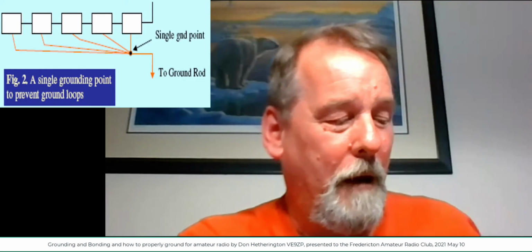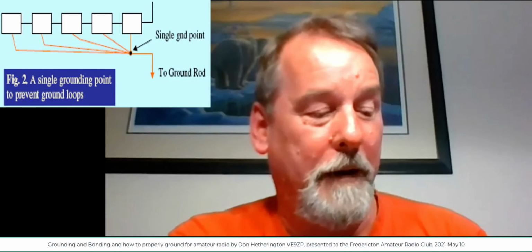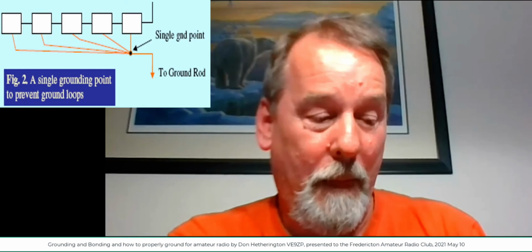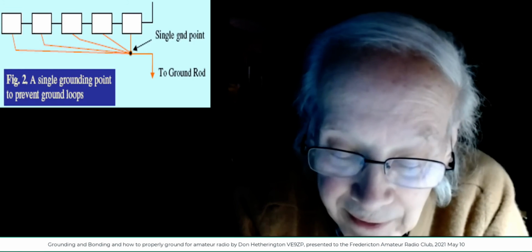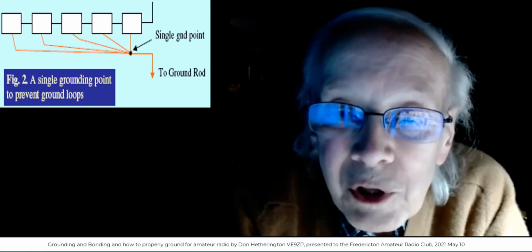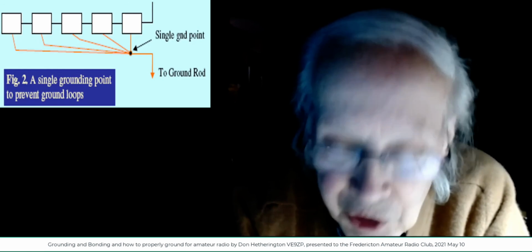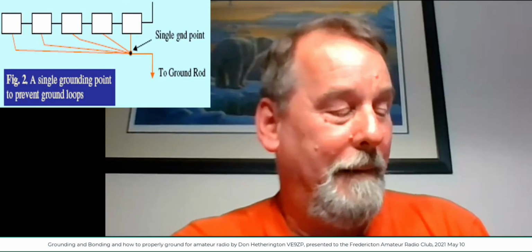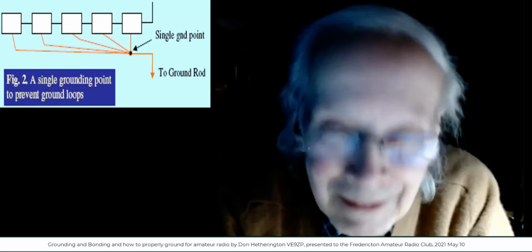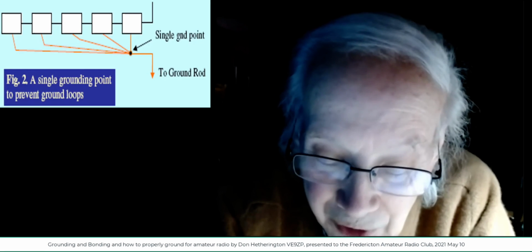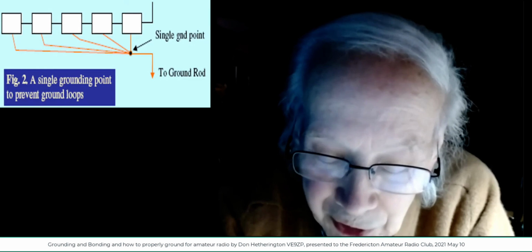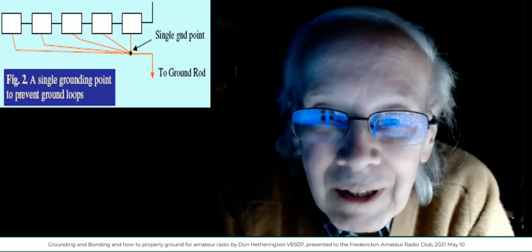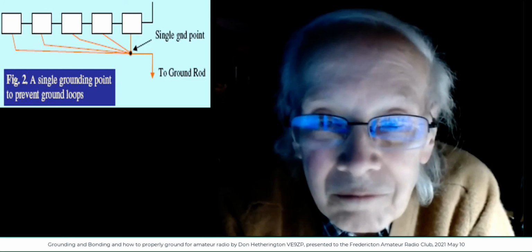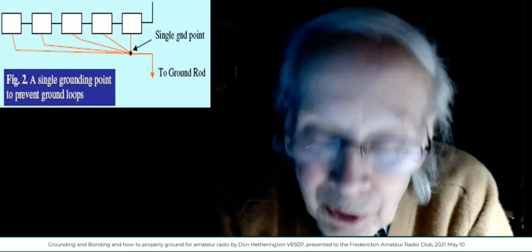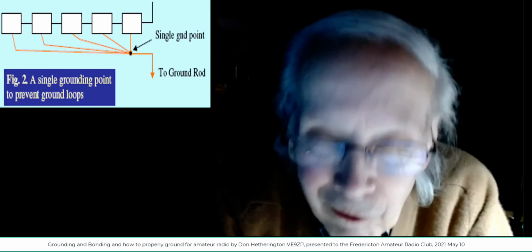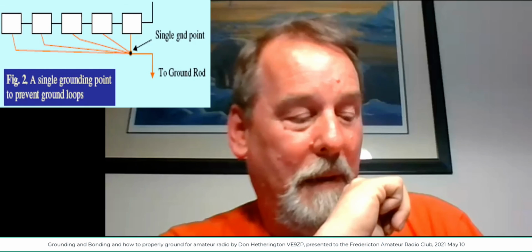I'm not quite following you, Bernie. We're talking about figure 2 with the single point ground, correct? Right, but there is a wire between the single point and the case of the devices, and there could be some RF or leakage current flowing through it, since it's not quite 0 ohms — there's still a very small resistance. There may be just a few millivolts, but that brings the potential of the two cases to a different level. And if you connect the two together with an audio cable or something else, you get a current flowing through that cable.